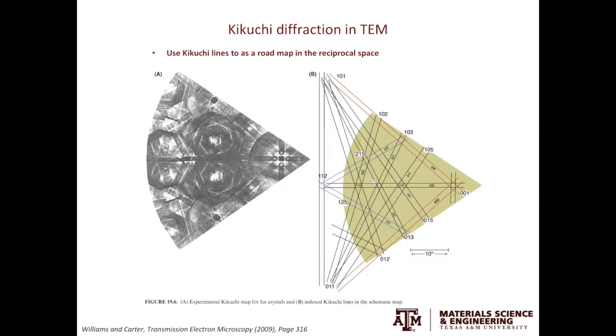The second use of Kikuchi lines in TEM is that we can use them as a roadmap. In many cases, for example if we are interested in taking high-resolution TEM images, we want to tilt the crystal to a low-index zone axis. Following the Kikuchi bands to where they converge together is usually where the low-index zone axes are. The third use of Kikuchi lines is that you can use them to determine the exact crystal orientation of your specimen in TEM. The principle is the same as that in EBSD, which I will not elaborate on here.